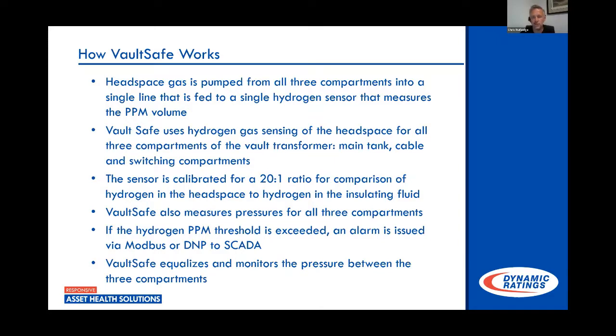And so the hydrogen is measured from each compartment as well. As I mentioned, those cables breaking down, that's a big PD event, a lot of hydrogen generated. And one of the things I really recommend when doing this is to look at hydrogen as a rate of change alarm. In all instances, actually, because I've seen transformers where 100, 150 parts per million is a pretty normal operating range for that transformer. What I'm concerned with is, did I gain 50 parts per million of hydrogen or 25 parts per million of hydrogen in the last 24 hours? When I see that type of event and that fast an increase in hydrogen, that's pretty much letting me know that I have some active PD occurring or some type of sparking event that's starting to go on.